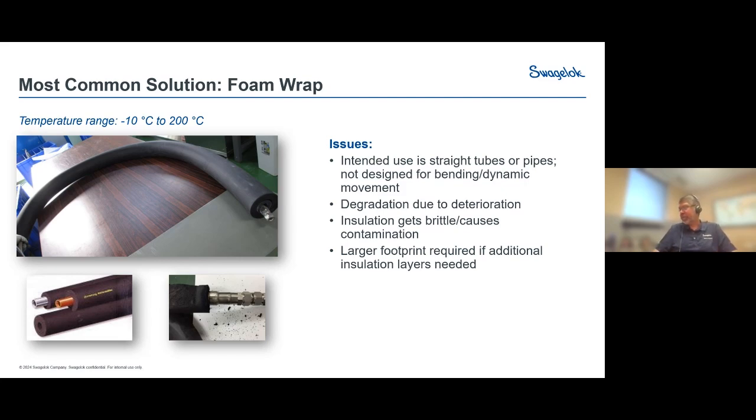We've seen people put covers on it and things to collect the flaking, but even that does not really work well, because as it starts to deteriorate and flake off, it does not do nearly as well insulating. To make this also insulate better, you need to put more and more layers on this, and it becomes a very large footprint as well. So it takes up a lot of space, and it tends to have poor performance over time.